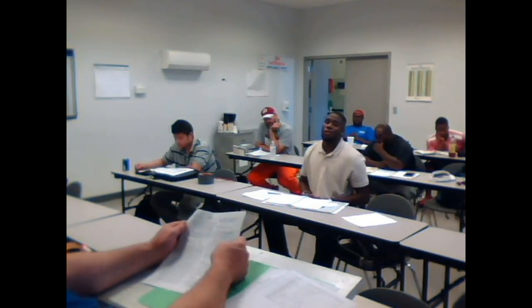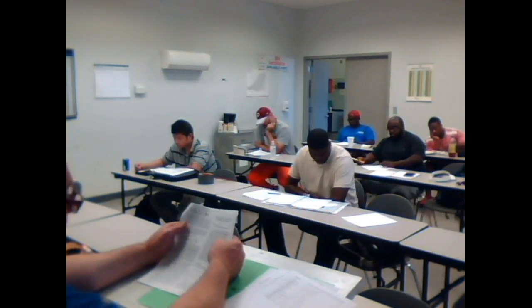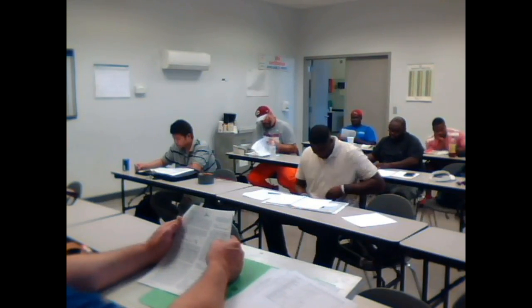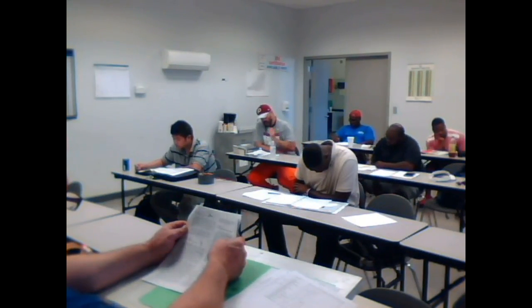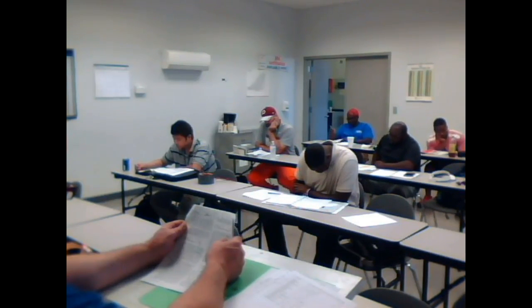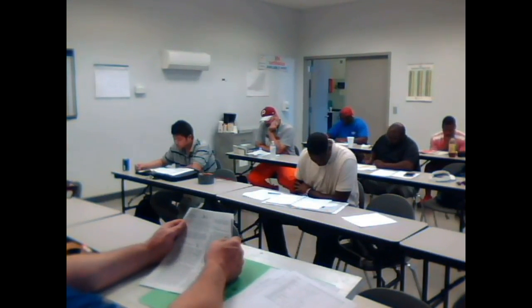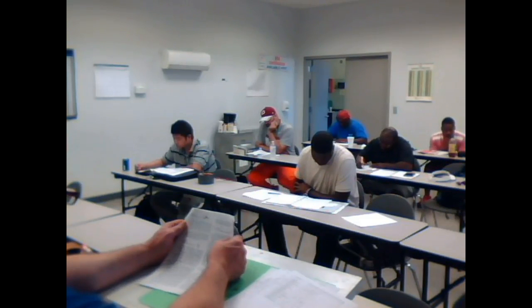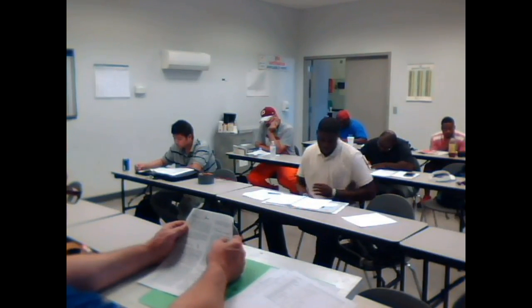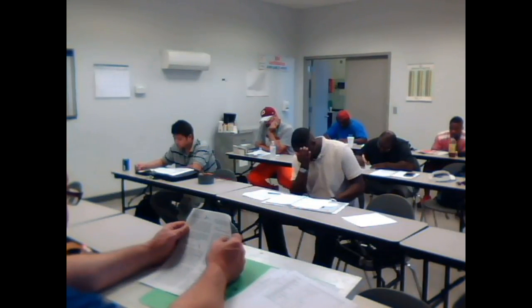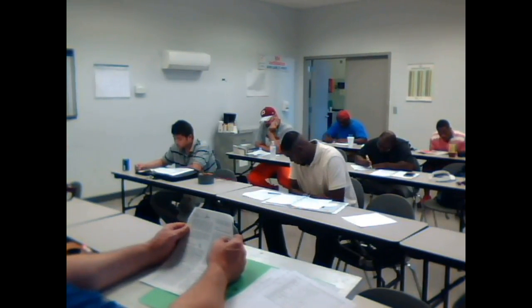Now let's look at 2615, shorted coil. Now this could be on a relay or a contactor. Excessive low or high voltage applied to a relay or contactor coil, the magnet, right, will cause excessive current draw, the same as a motor. This excessive current draw will cause overheating of the coil, break down the insulation between the windings, and result in shorts between the wire turns in the coil. Shorts in the coil reduce the magnetic power of the coil as well as increase the current draw.